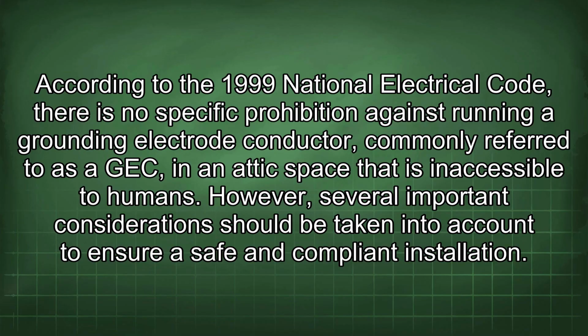According to the 1999 National Electrical Code, there is no specific prohibition against running a grounding electrode conductor, commonly referred to as a GEC, in an attic space that is inaccessible to humans. However, several important considerations should be taken into account to ensure a safe and compliant installation.